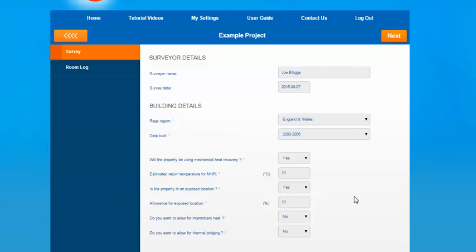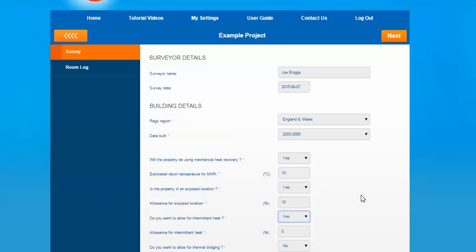The next question relates to whether the property or the install will be using intermittent heat. This is if the system is running for less than 16 hours a day — it'll be classed as intermittent heat. If it's more than 16 hours a day it's classed as continuous. If you select yes for this option it'll give you an option to add in an allowance for this. The domestic heating design guide states around 15% for intermittent heat, but again we haven't set it as a default option so that you can make a judgment on the property you are working on.